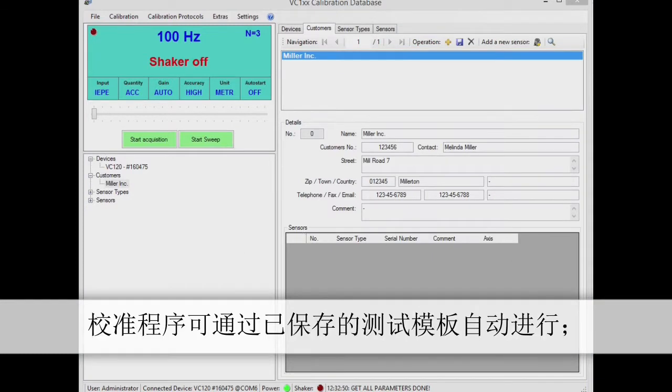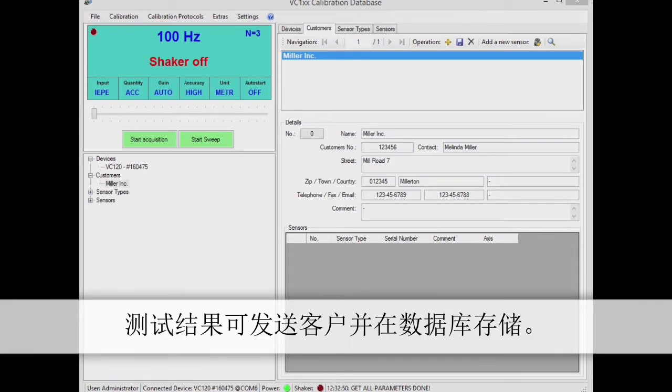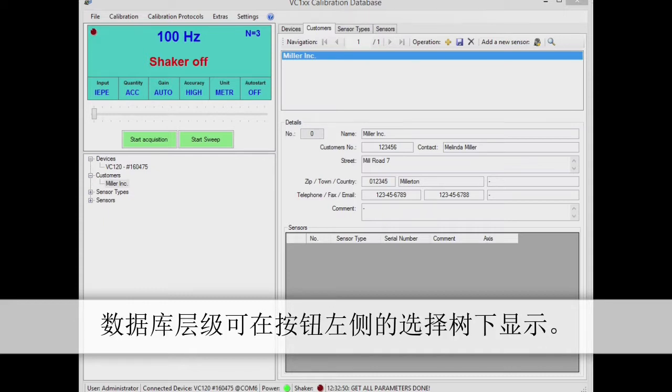Database supported calibration is by far the more practical of the two options. Calibration is carried out automatically in accordance with saved templates. Results are assigned to customers and stored in the database.